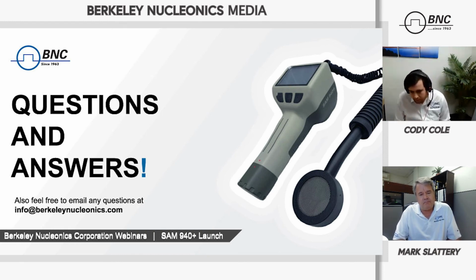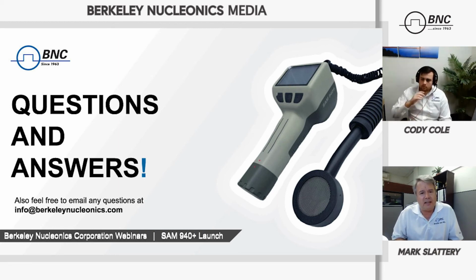Yeah, and to jump from that to over here, Charles Adams is wondering if there is a way to get the uncorrected counts per second displayed on the screen. Uncorrected counts per second. Are you referring to counts that have been subtracted from the background counts? Not sure if that is what the corrected counts are. I don't think we can do that in real time. What you are seeing on that screen is the actual counts, the total actual counts that the device is reading at that time.